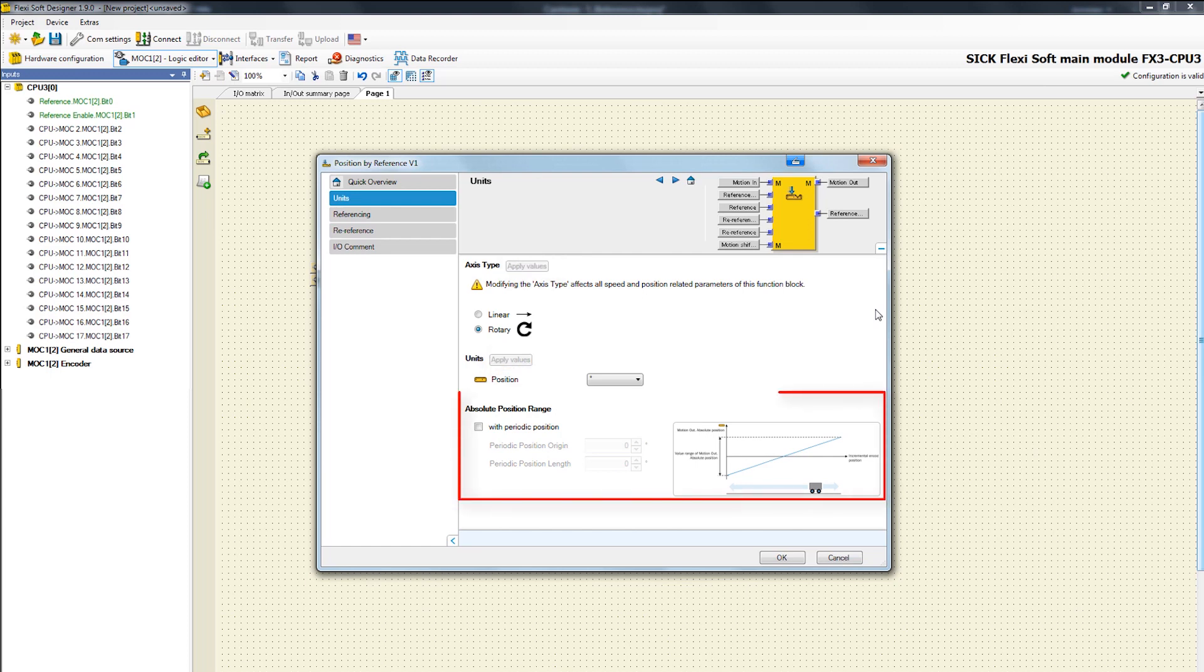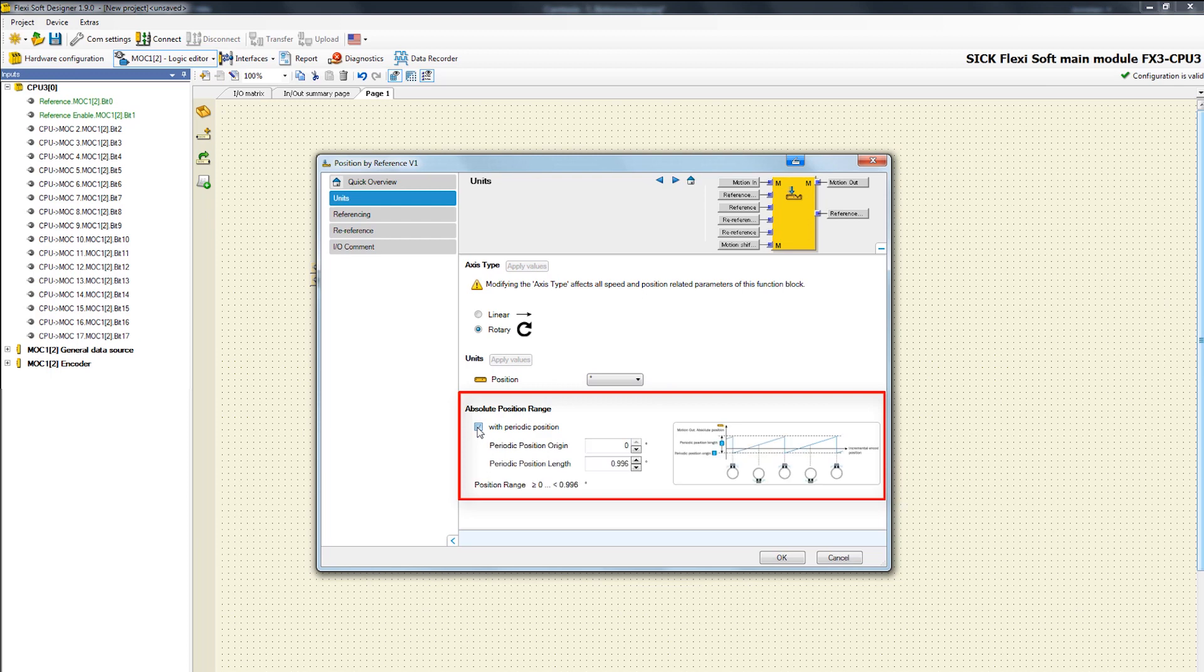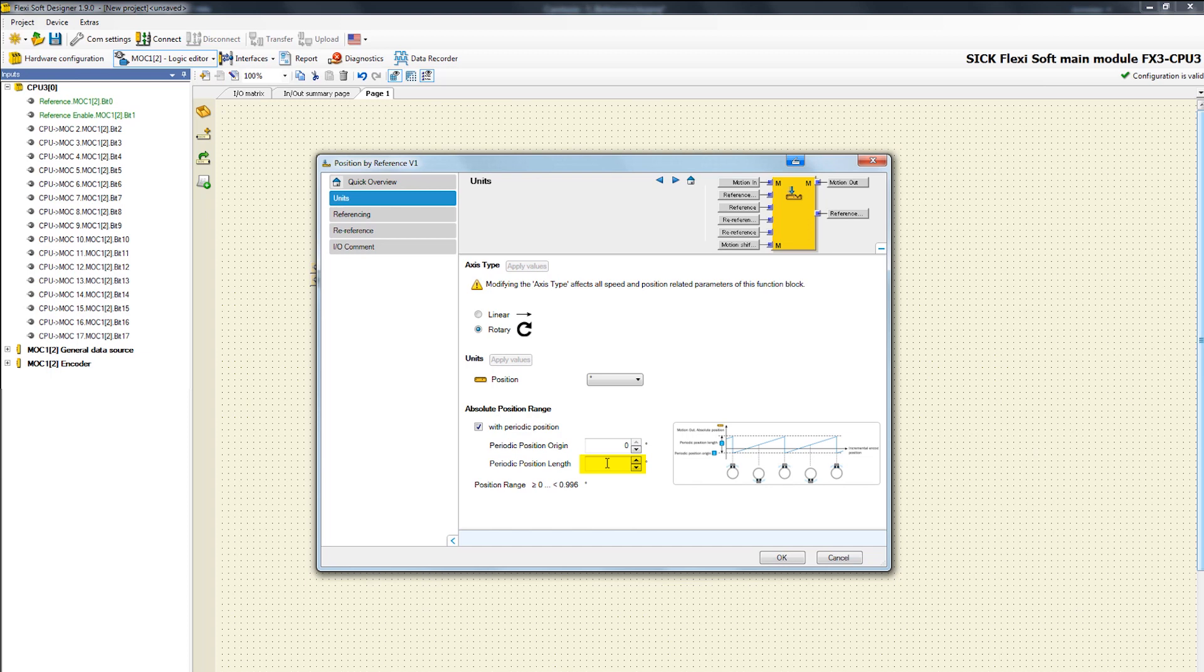There you can see the settings of the absolute position range. In our case we have to activate the periodic position window. That's because in our application the mechanical position is a periodic position like a mechanical press. There the beginning and end of the position range adjoin to each other. That means for example the mechanical position repeats every 360 degrees.